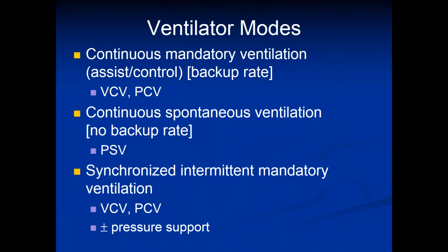The basic ventilator modes that are available on most ventilators today consist of continuous mandatory ventilation, continuous spontaneous ventilation, and synchronized intermittent mandatory ventilation. Now, continuous mandatory ventilation, also referred to as CMV, is an assist control mode which provides a backup rate, so there's a set rate, but the patient can also initiate breaths on their own, which would be a full-size ventilator breath. This can either be done in volume-controlled ventilation, or VCV, or pressure-controlled ventilation, or PCV.